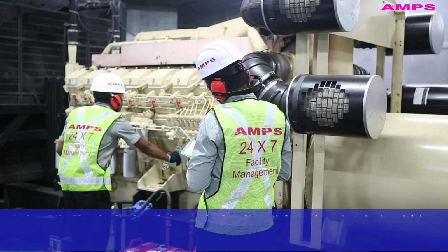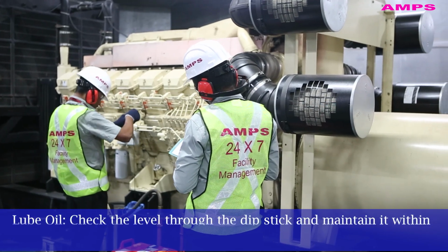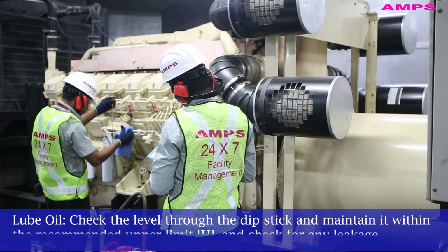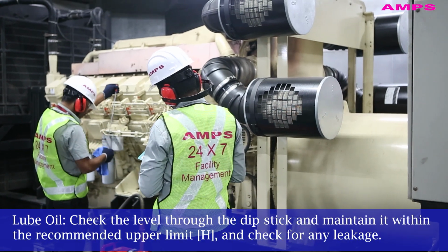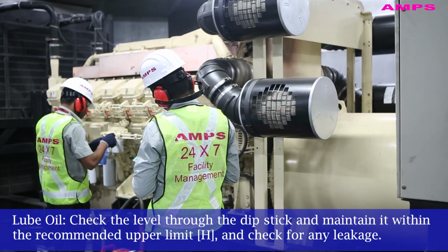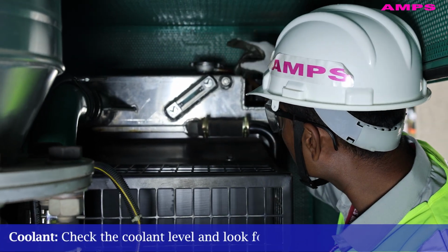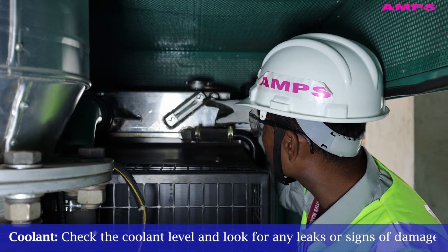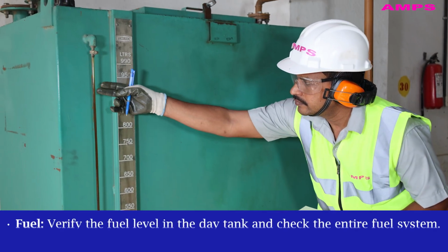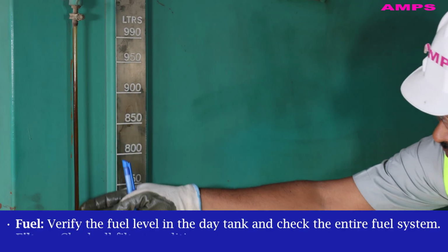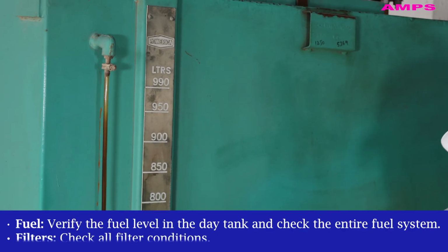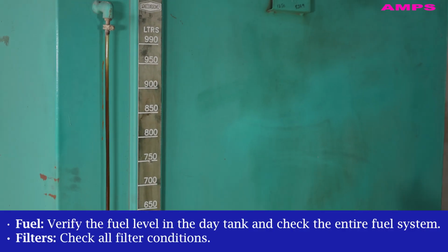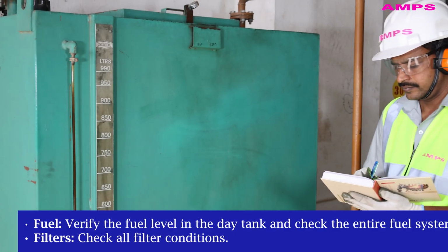2. Fluid levels and checks. Lube oil: check the level through the dipstick and maintain it within the recommended upper limit H, and check for any leakage. Coolant: check the coolant level and look for any leaks or signs of damage. Fuel: verify the fuel level in the day tank and check the entire fuel system. Filters: check all filter conditions.